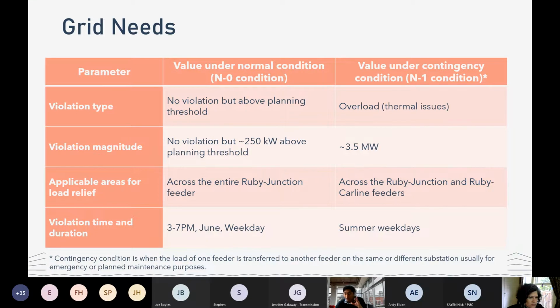To restate, Ruby Junction is where we've identified the issue, about 250 kW above the planning threshold that we want to mitigate at a minimum. And the expectation is that in an N-1 or contingency condition, when load has been shifted to Ruby Carline, we would need to alleviate another 3.5 megawatts.